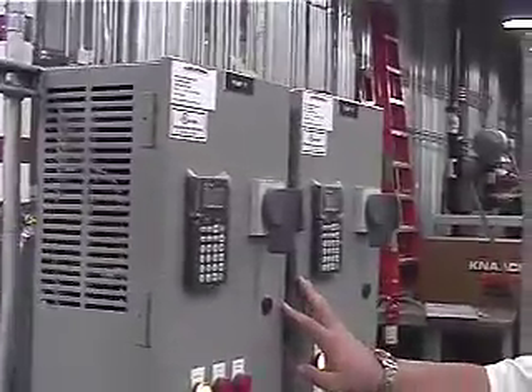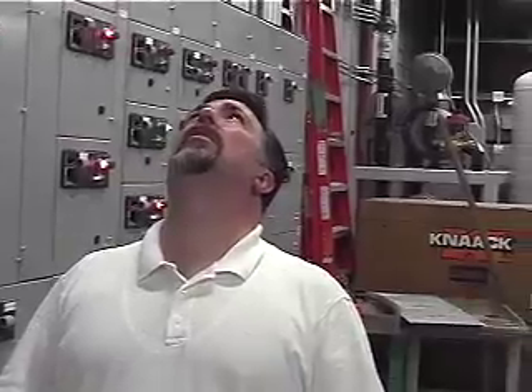These are the two pumps that operate to control your process control chilled water off the heat exchanger 3, right over here. So it's just that little guy there. There's pump 12 right there, and then pump 11 right there. Those two pipes right there, that's where they go into the outside air heat recovery coil. So that's the coil that shares off the lab exhaust. You've got your pipes coming in right there, and then they go across and through the pumps over there, to then feed over to the coil in the lab exhaust.